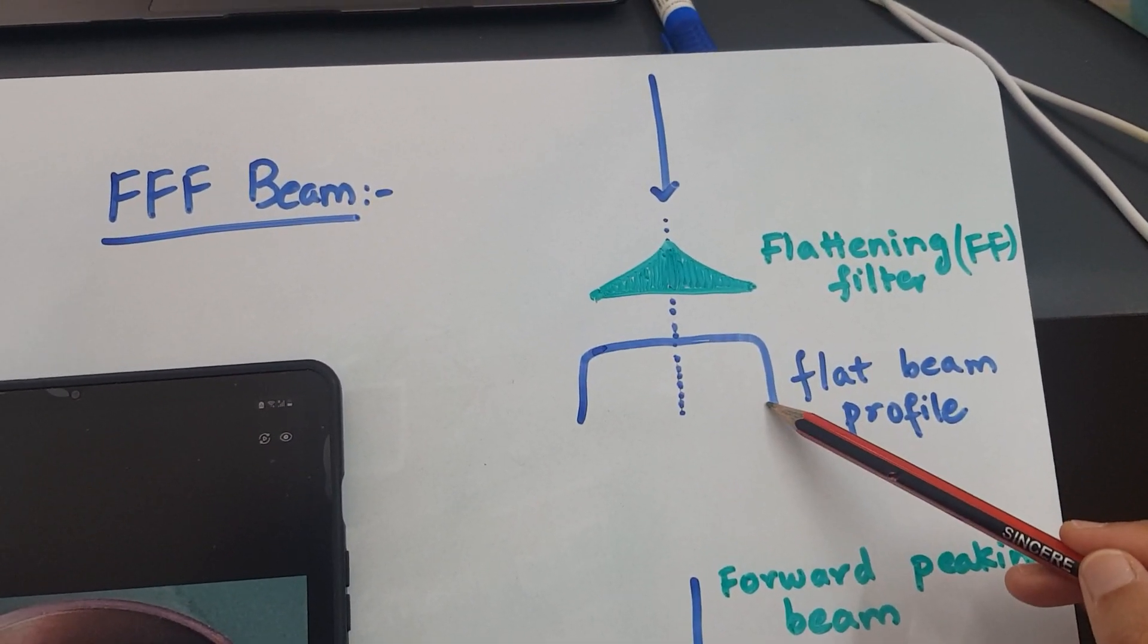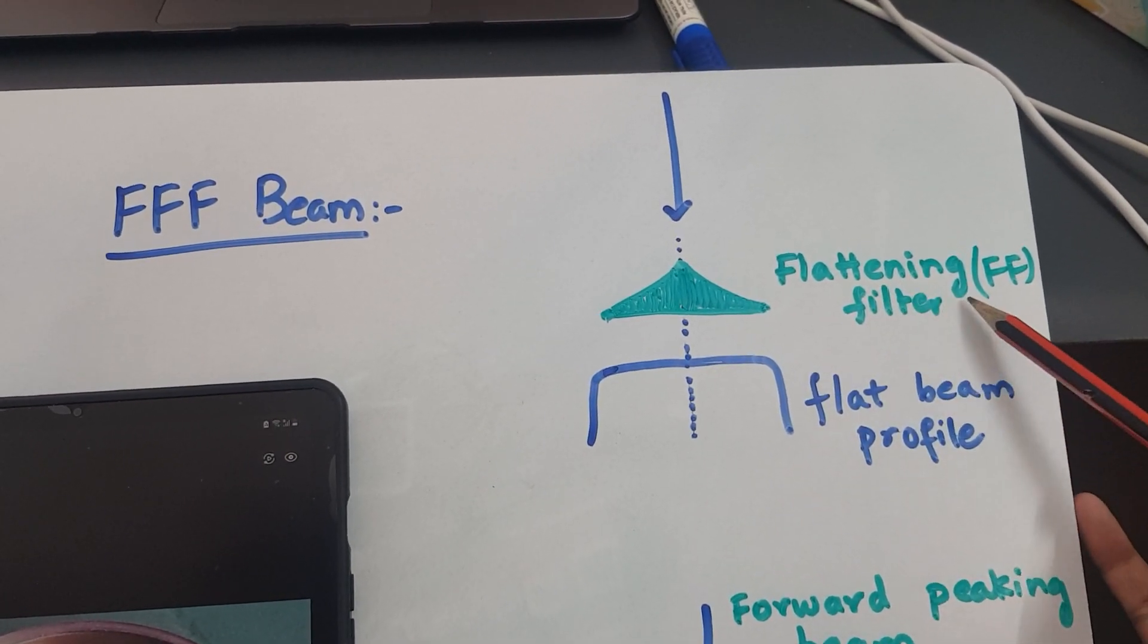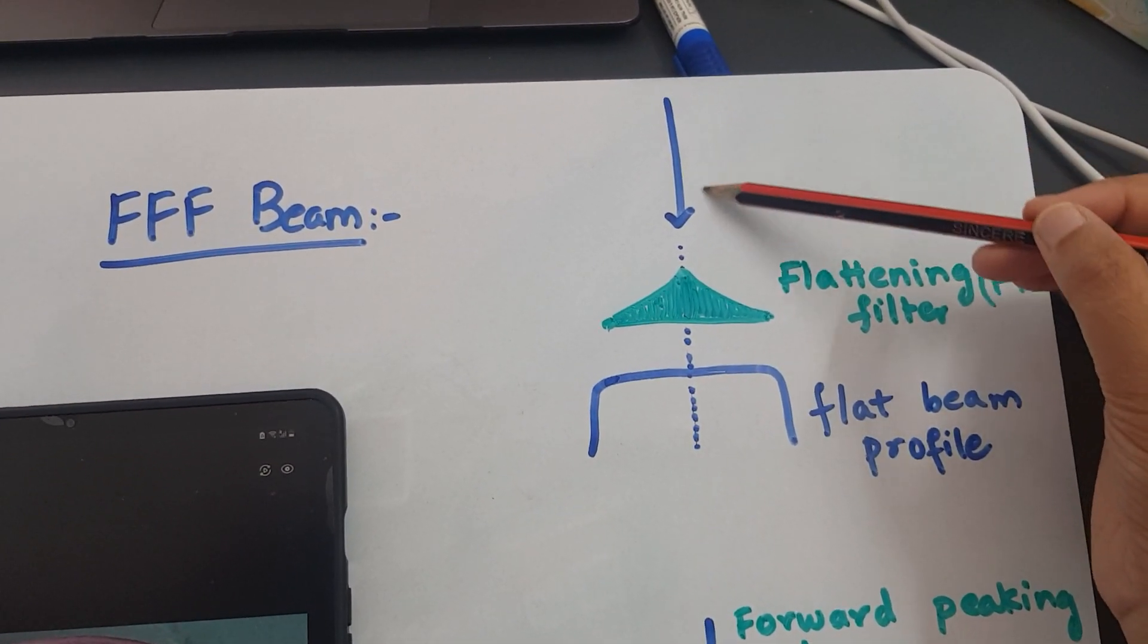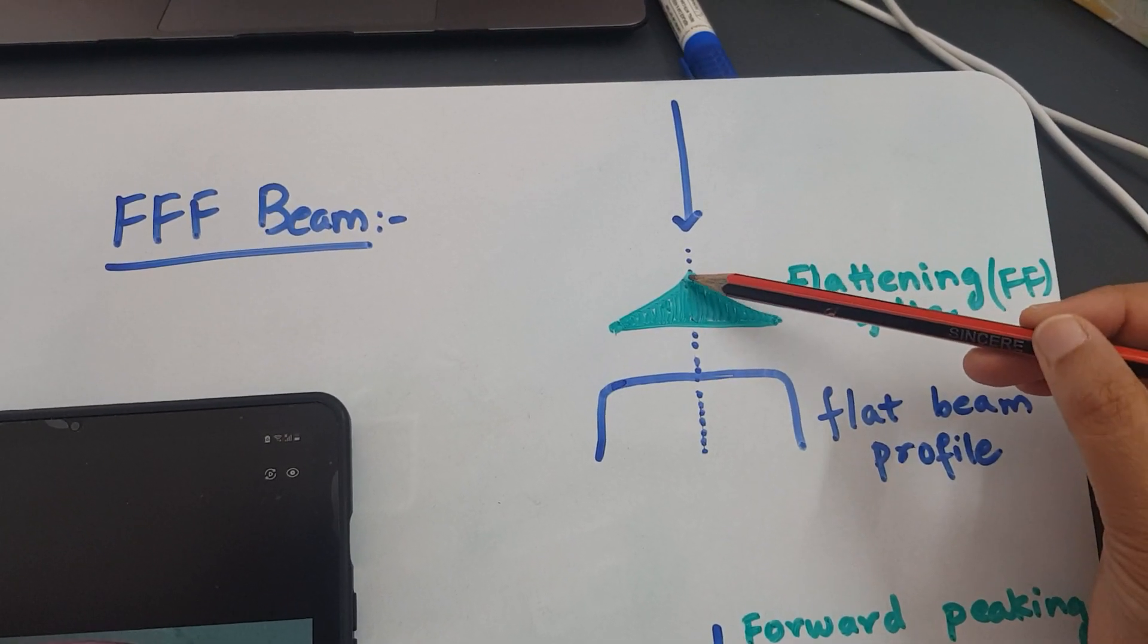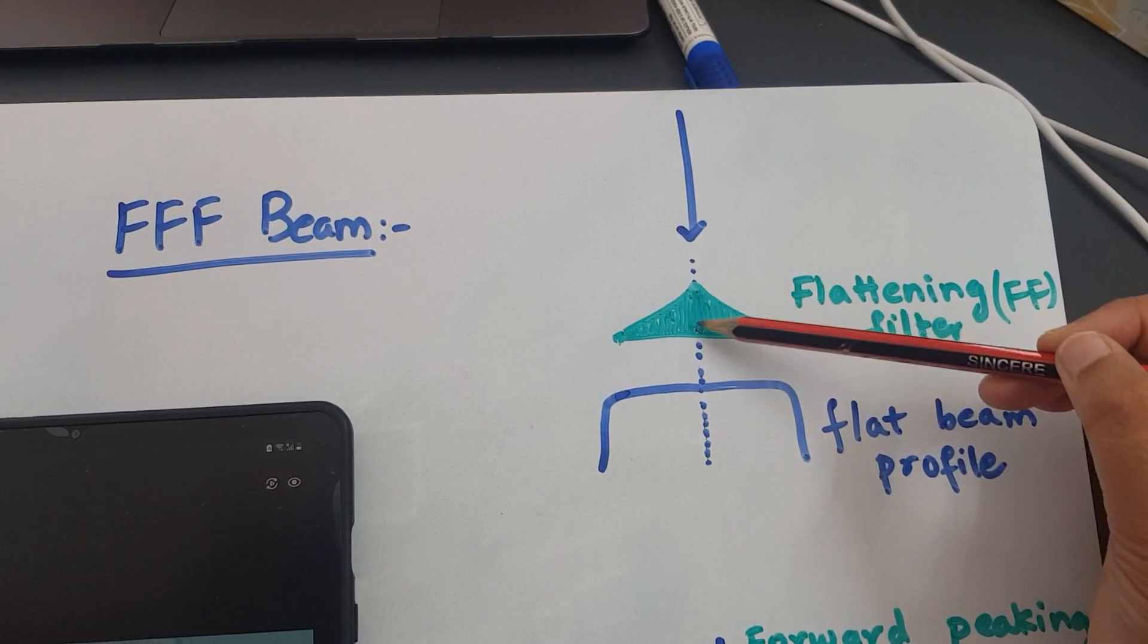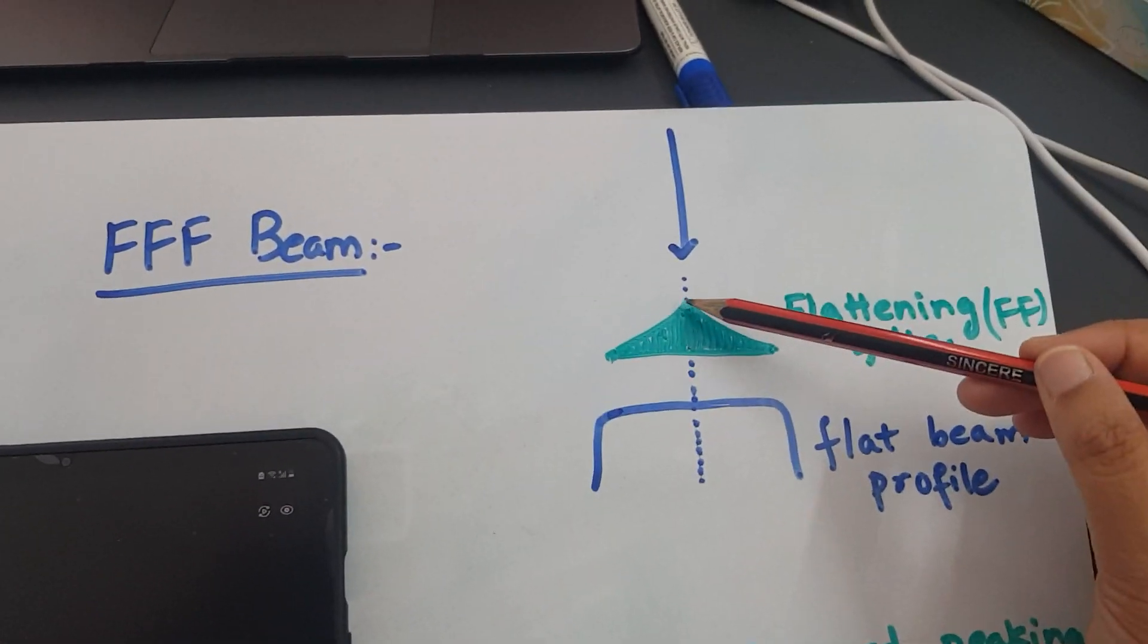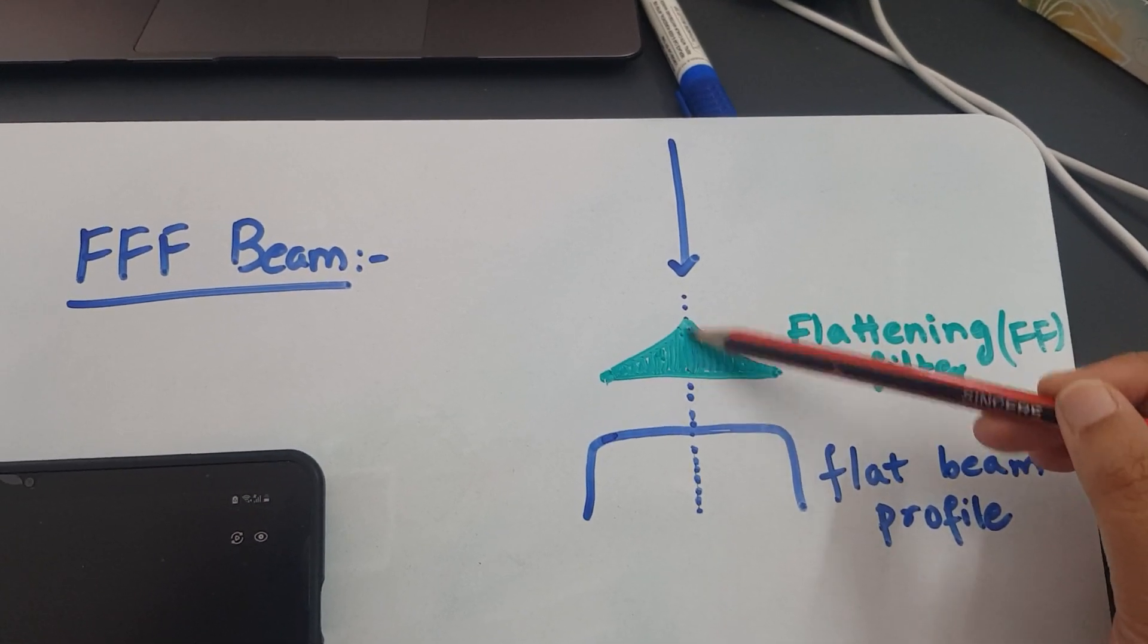This is how a normal flat beam profile looks like because we have used a flattening filter. There will be a forward peaking beam, and then this is the thicker end of the flattening filter and this is the thinner end. So here the attenuation for the beam will be more, here it will be less.